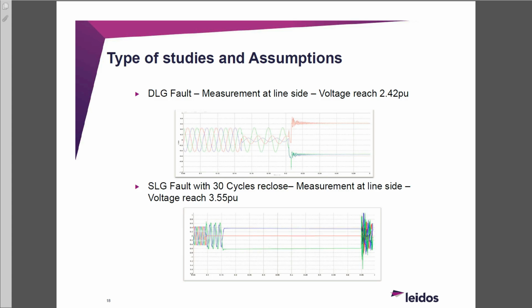So one thing we did, this one was 2.42, so it was above the client requirement. So we reduced the line by 5%, which gives an idea of how long the lines are that he's going to start to worry about. So when you don't do reclosing, reducing the line length matters, but if you have high speed reclose, it's not going to matter. You can reduce it and you're still going to see the TOV. It's not because of the length, it's because of the charge.